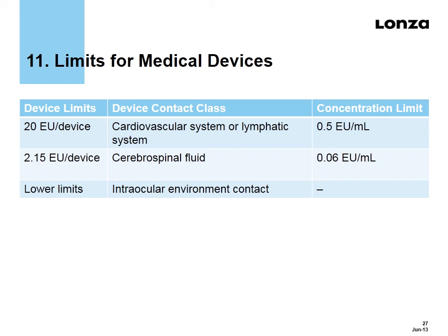If the device contacted cerebrospinal fluid, the limit would be 2.15 EUs per device. And again, using the 40 ml extraction volume, the limit would be 0.06 EUs per ml.